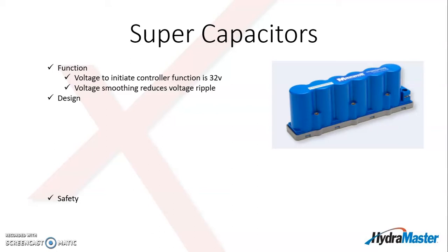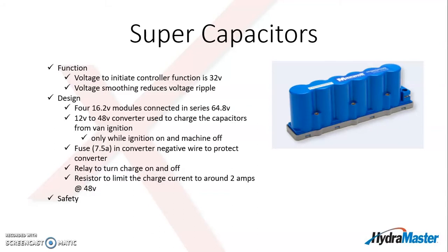The motor controllers will initiate operation at about 24 volts. However, at 24 volts, there's not enough power in the capacitors to keep the machine running, so we generally advise to not start the machine until capacitors are charged up to at least 32 volts. The design of the capacitor pack, again, is 4 16.2 volt modules. They're connected in series, so it gives us a capacitor pack voltage rating of 64.8 volts.